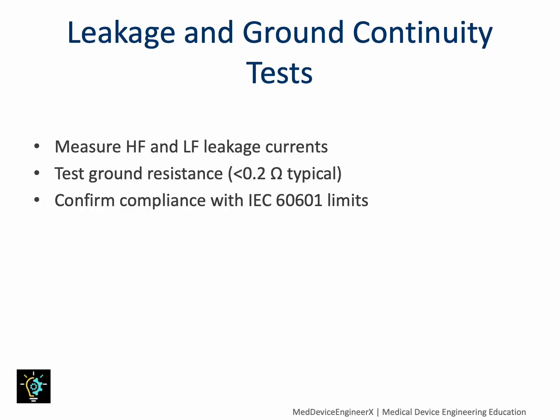Leakage and grounding are the foundation of electrical safety. Use a safety analyzer to measure ground resistance. It should be below 0.2 ohms. Next, check both low frequency and high frequency leakage. The high frequency leakage must stay within 150 milliamps, while chassis and patient leakage follow IEC 60601 limits. These results prove that insulation, shielding, and grounding paths remain intact, preventing any current from reaching the patient or operator.